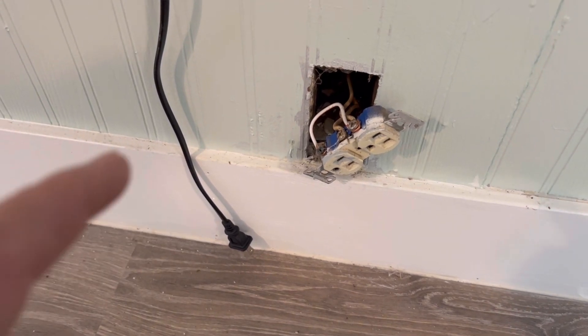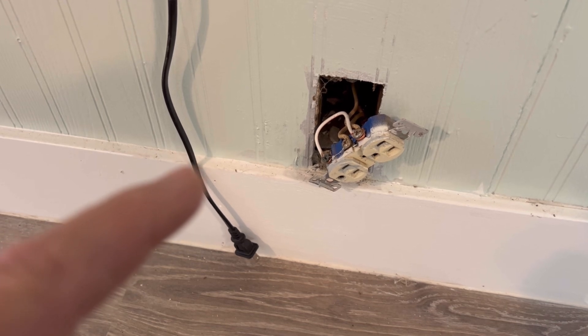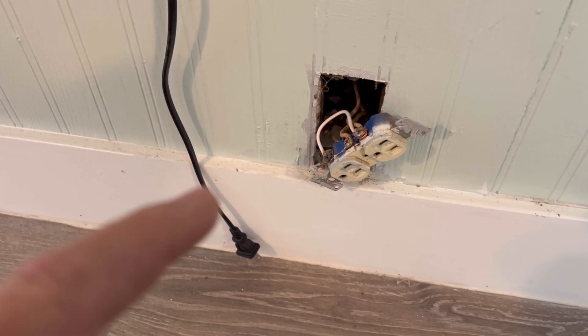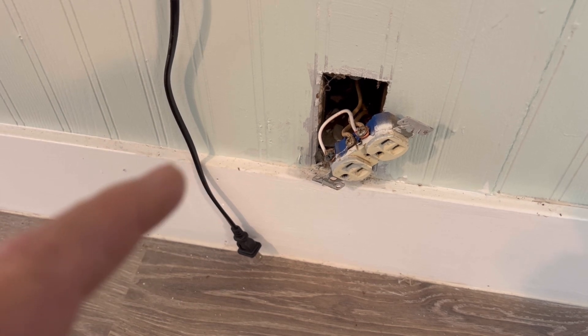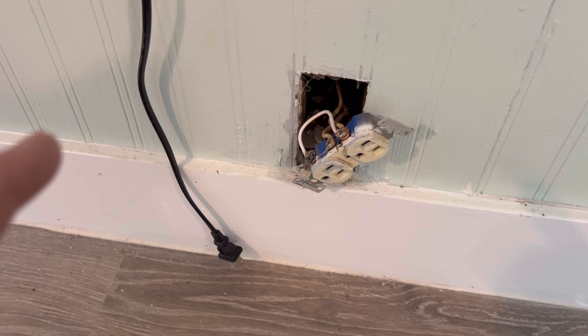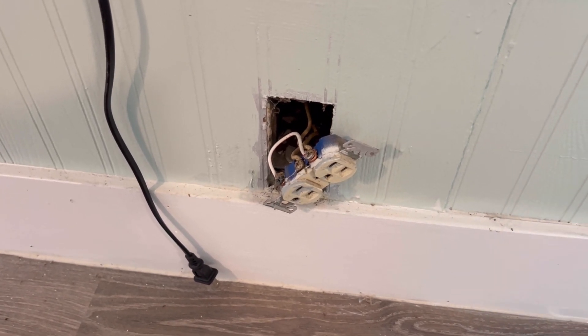Whoever did this intentionally did this. This is pretty dangerous because it creates a bootleg ground and a potential fire hazard on the receptacle. I'm assuming that there are a few more like this — let me go pull another one and let's see how it looks.